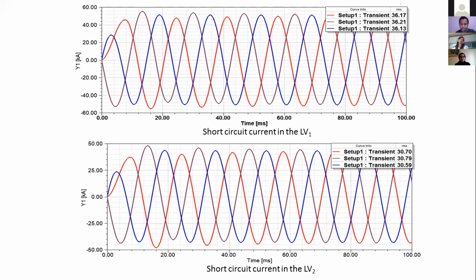In this page, you can see the three-phase short circuit current of the low voltage winding, the inner low voltage winding, which is calculated at about 36 kiloampere. And in the bottom figure, you can see the three-phase short circuit current relative to the outer low voltage winding, which is calculated at about 30 kiloampere.